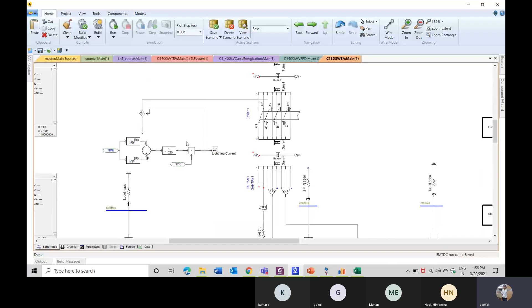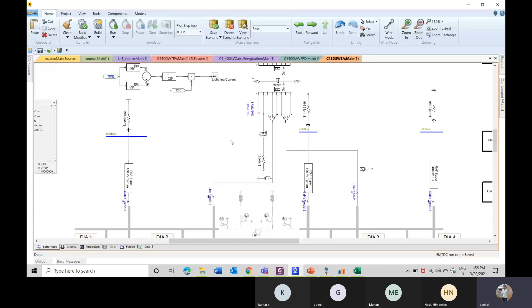But here what we have done is we have artificially created a lightning current because this tower is much closer to the substation. When the lightning hits on the particular tower which is near the substation, what impact this lightning current will create inside my substation, that is what we are going to analyze in fast front overvoltage studies.